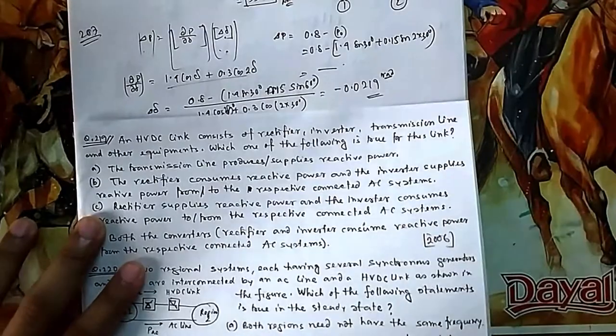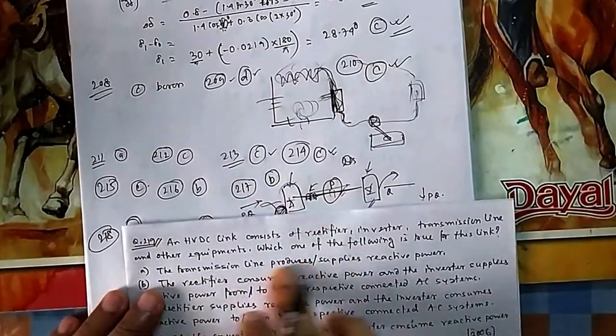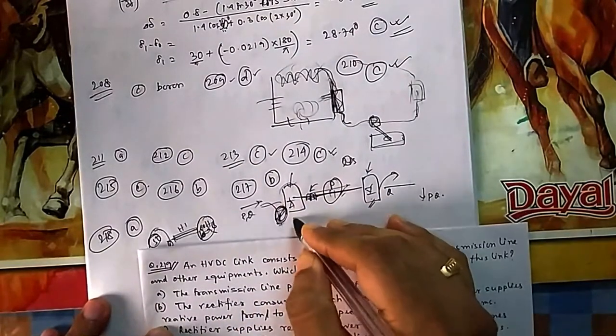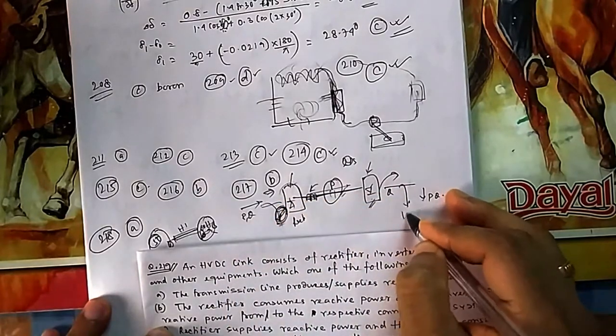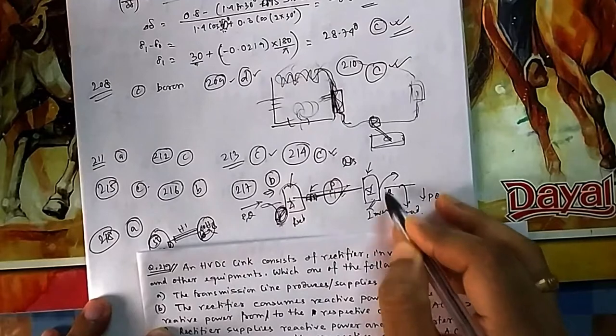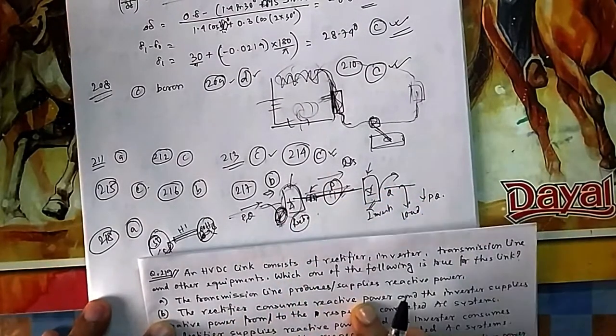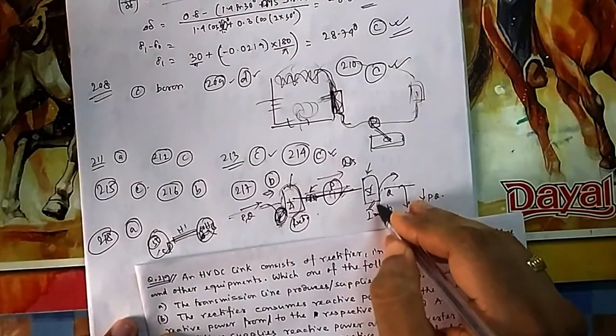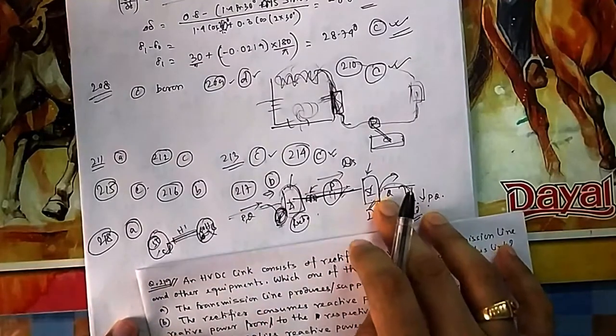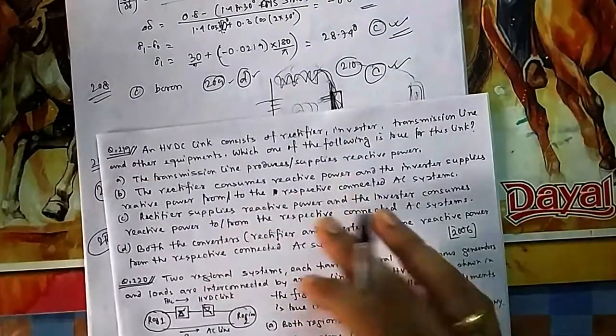Question 219: in an HVDC link consisting of a rectifier, inverter, transmission line, and other equipment — which of the following is true? The transmission line carries no reactive power Q, so option A is wrong. From the AC source, both P and Q are supplied, but only P flows through the DC link. Therefore the rectifier consumes reactive power, and the inverter supplies reactive power to the load on its side. So the answer is option B.